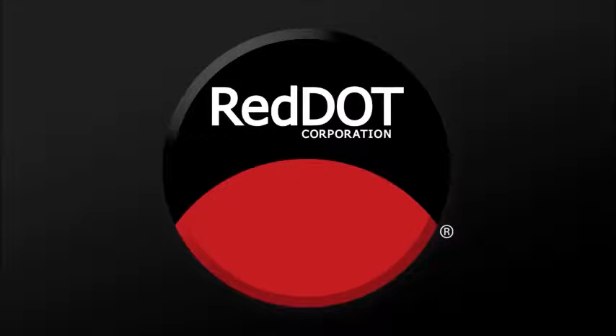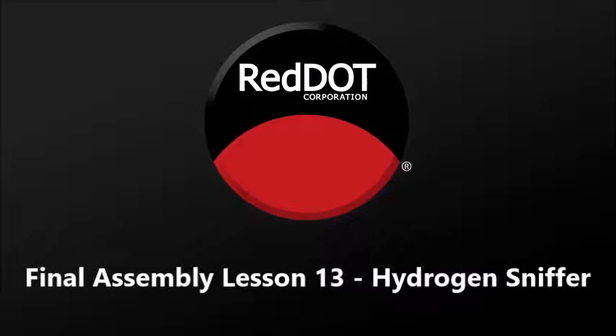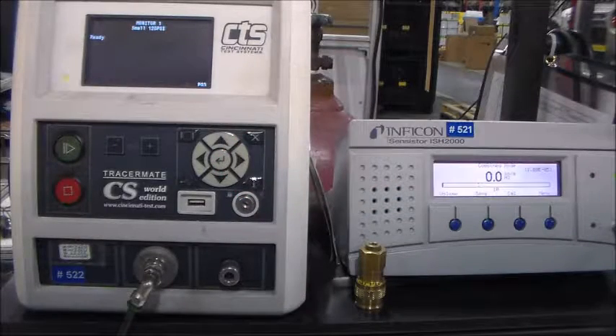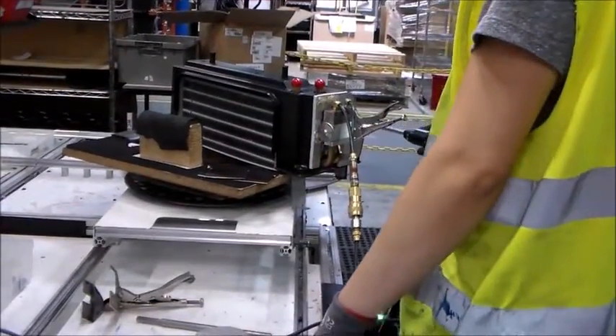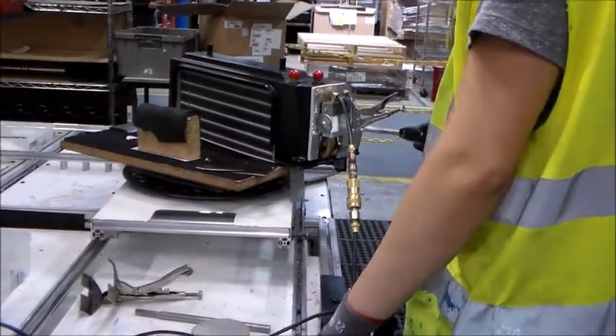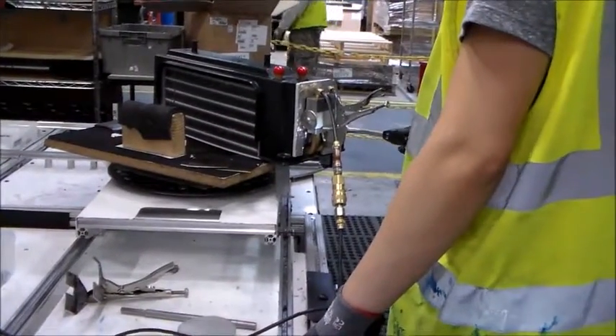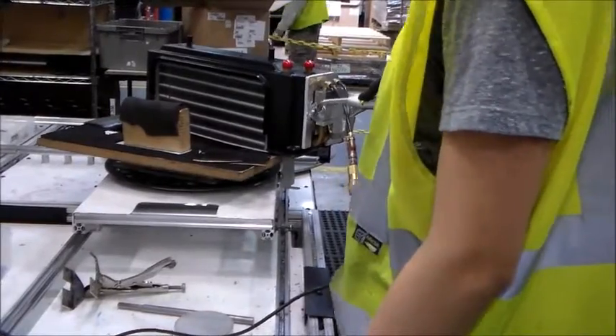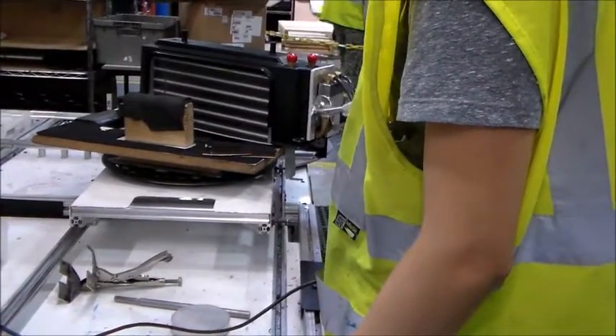Hello, today we will be learning about how to operate the hydrogen sniffer. The hydrogen sniffer is a combination of the Inficon hydrogen leak detector sensistor ISH2000 and the Cincinnati TracerMate CS connected to a vacuum pump. The sniffer fills the unit up with the gas at a specific PSI and then, using the testing probe, checks for any leaks from valves or fittings and displays the results on the screen.